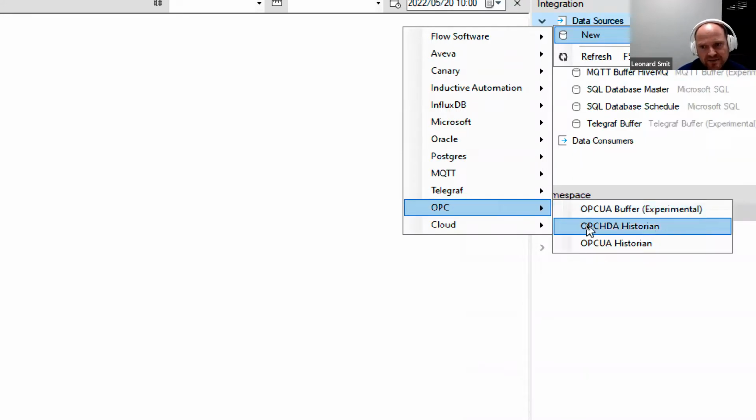We always had the capability to consume historical data from OPC, but now we have the capability to consume OPC UA data and buffer this. We only buffer this data for 7 days. The reason being that you would use the point normalization and the period normalization to store this resultant aggregate or KPI in your database. And after that, we will then just clear out this real-time buffer.